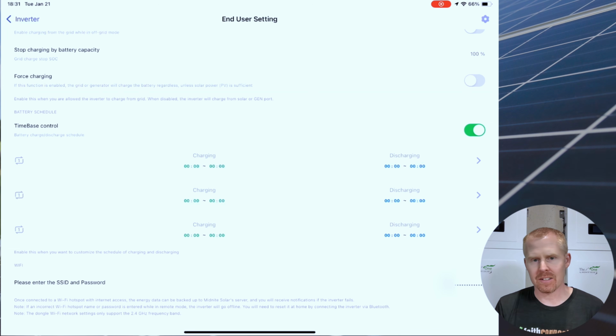So if you have it set to discharge between 10 a.m. and noon, it is going to try and push as much power as possible up to the grid to discharge your batteries during that set time frame.